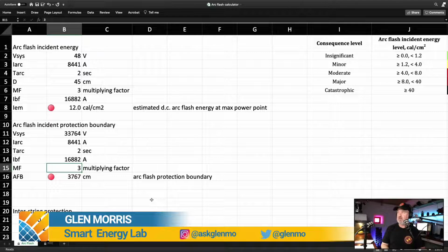So looking over here, where are we? We need to fill out these fields here. What's the battery system voltage? Is it 24 volt? No, it's not. It's a 48 volt system. I'd actually already started filling this one out before we started this event. The arcing current is actually calculated. It's the bolted fault current, this one here, divided by 2.